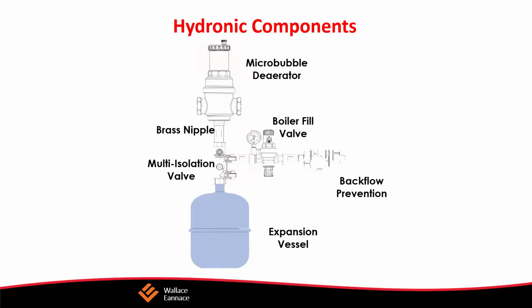There are other kinds of expansion tanks. Sometimes you'll see an expansion tank that looks like this. That's a compression tank. Most of the time, what you see is one that looks like this. This is a bladder tank. These are what's put in mostly now. The compression tanks are older systems, and even if they're in there, they're usually going to be replaced by this. You can also get some commercial pre-charged tanks or some diaphragm tanks.